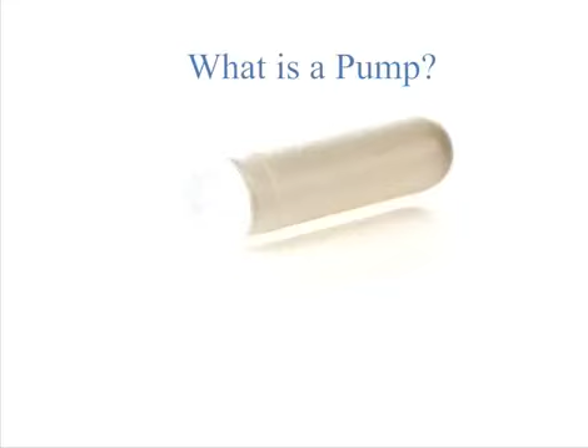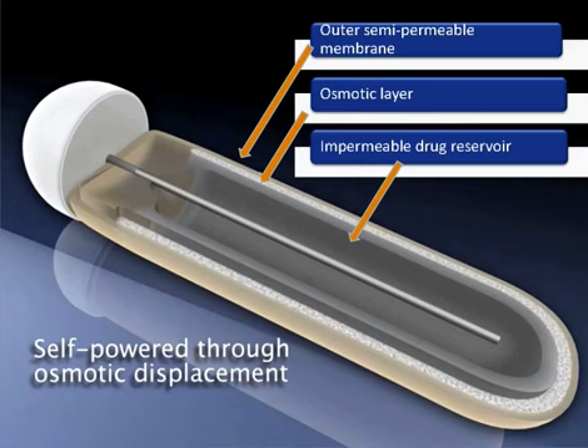There are 3 layers to every pump. The outermost layer is a semi-permeable membrane. The middle layer we call the osmotic layer. And the innermost layer is the impermeable drug reservoir. Once the pump is filled and implanted, the pump works by absorbing interstitial fluid from the animal, and this is done via osmosis. Specifically, the osmotic pressure difference between the middle osmotic layer and the tissue environment outside the pump is what causes interstitial fluid from the animal to travel through the semi-permeable membrane.